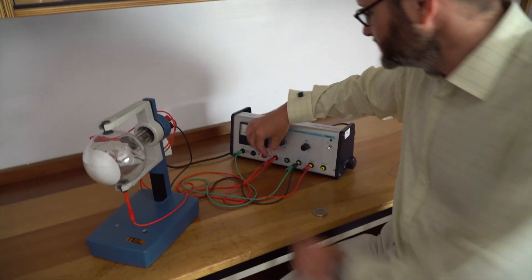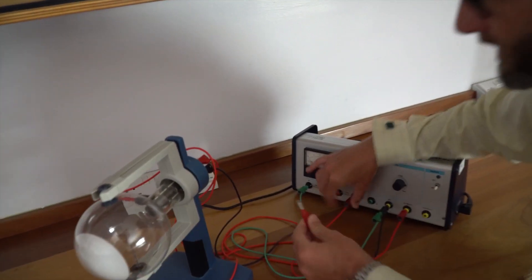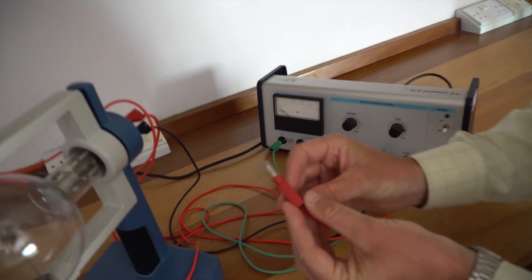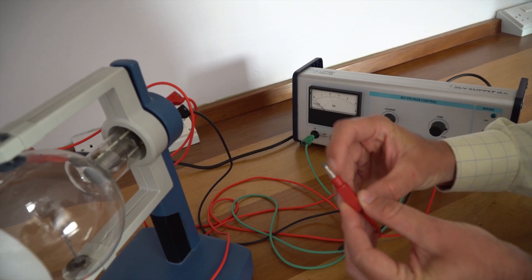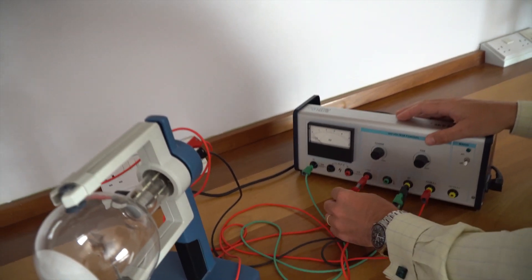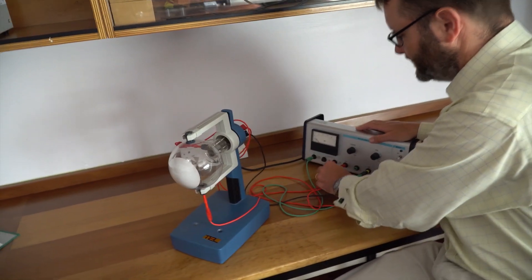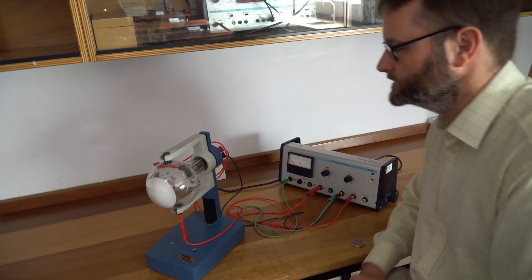Are you using shrouded leads? I'm also using shrouded connections. These look like normal four millimeter plugs, but they've got retractable plastic shrouds. So you can't half plug it in and have a live connection available that you can touch. That's really important to make sure you use those.